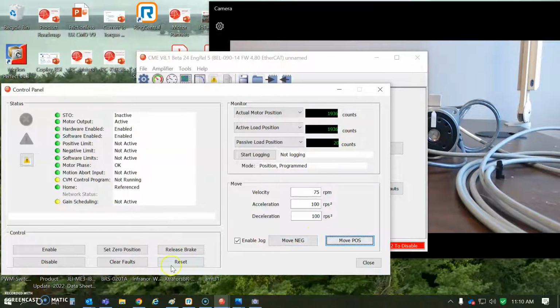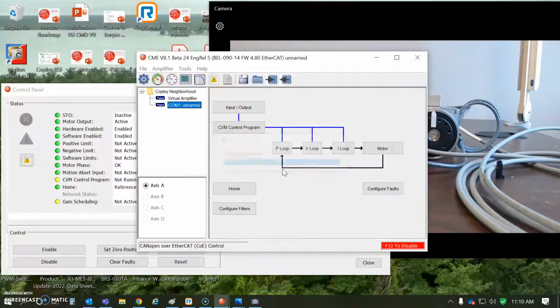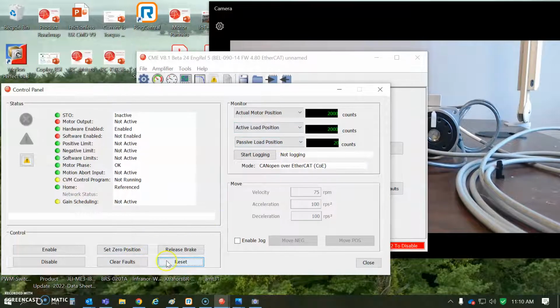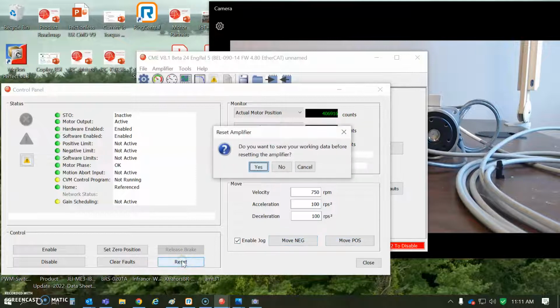There's the wrap. And I'm going to reset the drive. They should both wake up in the right zero position, because I'm in the zero position. So nothing's really changed. Enable the drive. And then let's just jog it a little. Yeah, so both are zero. Now what if we woke up in this farther position? It's within one wrap of the load, and it's multiple turns of the motor. We ought to wake up at this count after reset. So we give it the 4096 approximate. There, that's close enough. So reset.